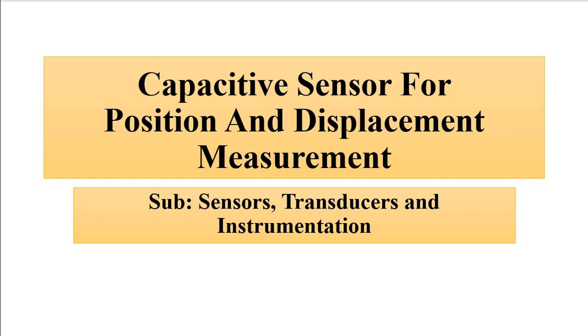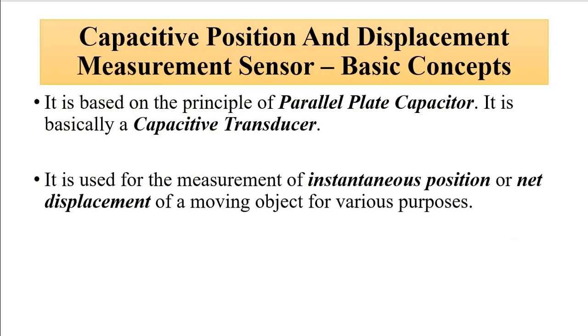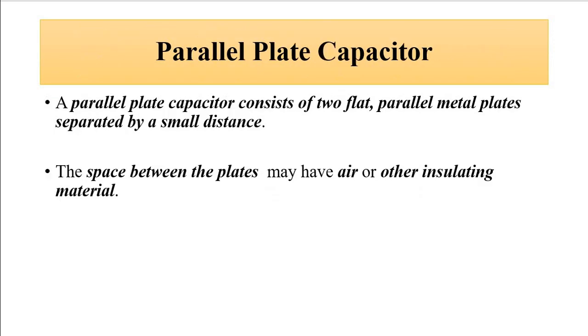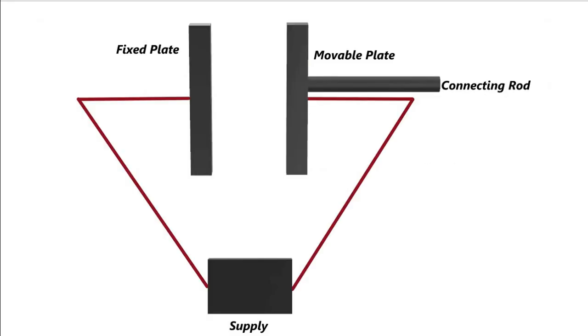The basic operating principle of any capacitive sensor used for measurement of any physical parameter is based on the principle of a parallel plate capacitor. It consists of two parallel metal plates for sensor purposes. One of them is fixed, and the other one is movable. It is connected to a rod which is connected to the object whose displacement or physical parameter is to be measured.